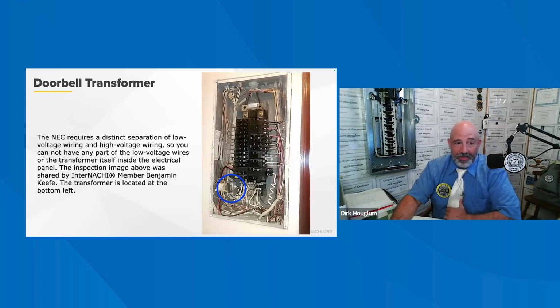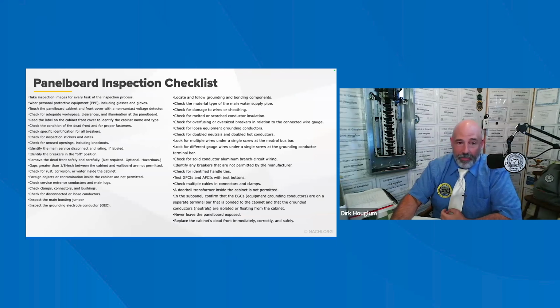The NEC requires a distinct separation of low voltage, so you should not have a doorbell inside. That causes significant issues, and you can see that in NEC 725.16. The panel board checklist, I would just take a screenshot of this because we are not going to have time to go through all this. At least I don't think so. I'll give you a few seconds.